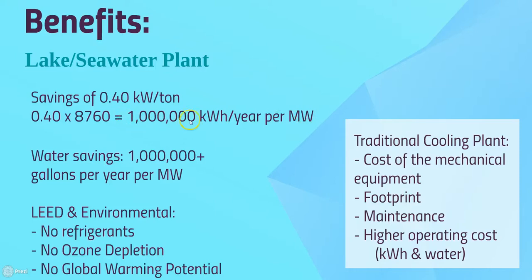So that's kind of that rule of thumb that you can use whenever you're trying to judge whether or not it might be worthwhile and whenever you're doing the pricing on such a system. Now, we touched on the water savings before, but essentially this is going to be very location dependent. Whether you're in a wet or dry location, whether you're north or south, if you're a hot location, you're going to be burning more gallons of potable water per year per megawatt, and your savings over that is going to go higher, towards the 2 million gallons per year.